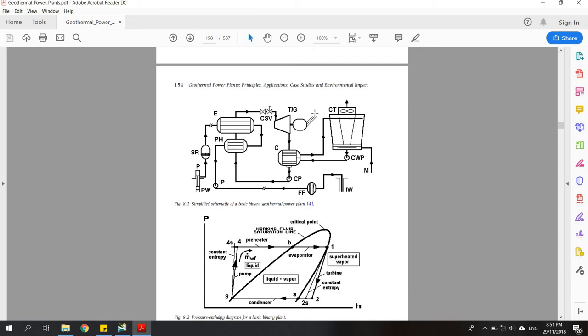After the turbine extracts energy, the working fluid will be cooled down, because the temperature after leaving the turbine is still quite high. We need a lower temperature in order to be able to extract heat from the geothermal brine, that's why we use a condenser. The condenser will be connected to a cooling tower using an air cooling system.